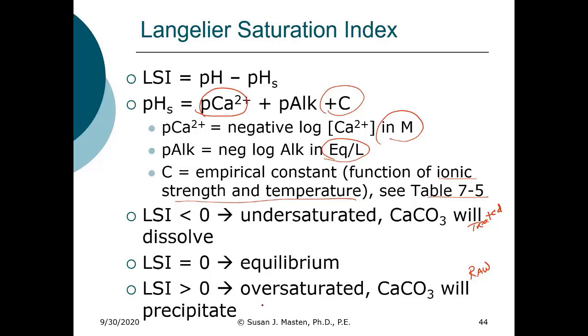So if the LSI is less than 0, that means that it's undersaturated and that calcium carbonate will dissolve. If it's equal to 0, you're at equilibrium. If it's greater than 0, you're oversaturated.